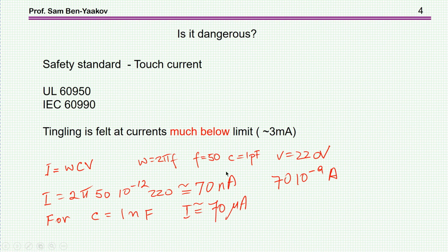Now, if we're talking about a capacitor at line frequency, let's take an example: suppose the capacitance is 1 picofarad at 50 hertz. Then the current is omega C times V. V is 220 volts, the European line, and you calculate it to be 70 nanoamps for 1 picofarad. If the capacitor is 1 nanofarad, 1,000 times larger, the current will be 70 microamps, way below the 3 milliamp limit.